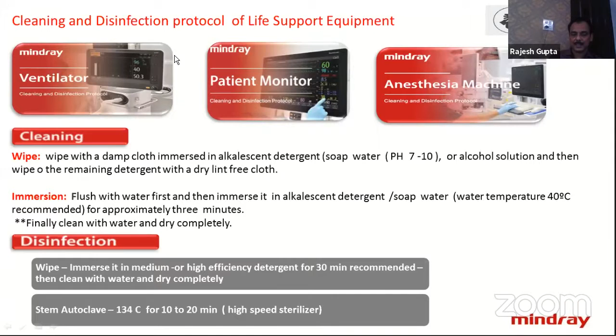For the cleaning process, simple soap water with a pH value of 7, and 75% ethanol for all the anesthesia machines. Sodium hypochlorite bleach is a good disinfectant, and 10% is the concentration for all the other machines. So here we have other things, isopropyl. Basically in India, we mostly use sodium hypochlorite bleach with a concentration of 10%, and 70% isopropyl disinfectant is available. But this recommendation is only for this COVID-19 era. Later, we need to take care as per normal maintenance and the recommendation of the manufacturer.